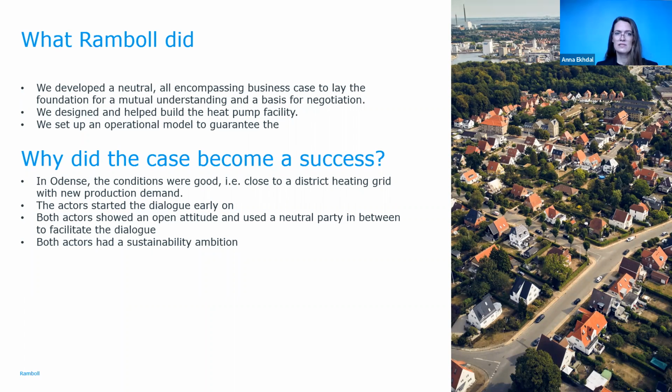And what were the key success factors in this case to make this happen? First of all, in Odense, the conditions were good. As Jesper has already brought up before, it's good to be close to a district heating grid, which it was, but the district heating grid was also in need of new production demand. So consider this when you are placing your data center. If you want to have a heat recovery solution, then you need to consider this when choosing your site.